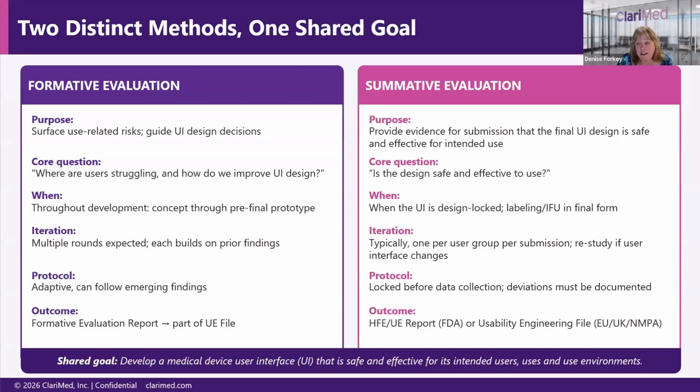Number one, I like to think of formative evaluations as those evaluations that are helping to form the user interface into what that final user interface will look like, making sure that it's safe, making sure it's effective, people can use it. And second, if you don't do formatives, you're going to have a very expensive summative that will turn into a formative, and it'll end up costing you lots of money in the long run. So we like to encourage people to do those formatives, make sure that your product user interface is evolving appropriately. You're identifying potential use errors and risks. You're optimizing the usability of that product, making sure that you're designing the right device for the right user in the right use environment and the right intended use.